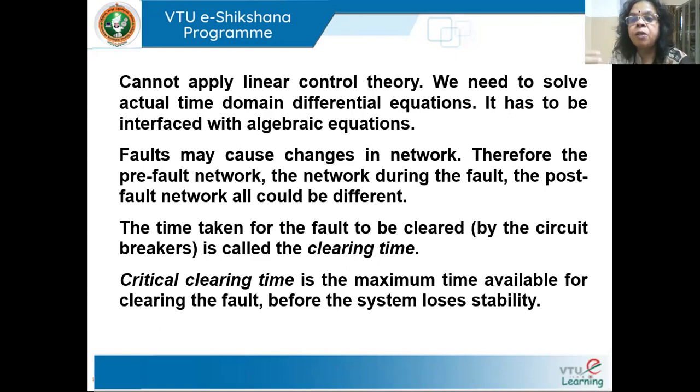And when you're planning a control, you have to plan what is the next step I would take if it occurs. So in contingency analysis, we plan, right? Right now, no fault has occurred. But if faults occur, what is the most severe fault and how will I take care of it? What control action do I have to take? So the operators will be prepared for it, and if the fault occurs, they can immediately execute the control which they have decided on. So that's why it is very important.